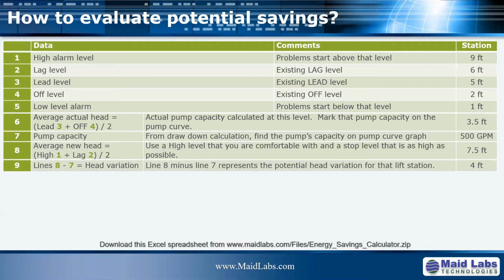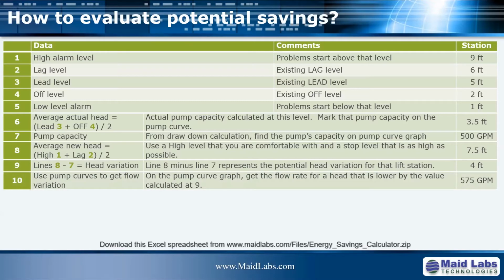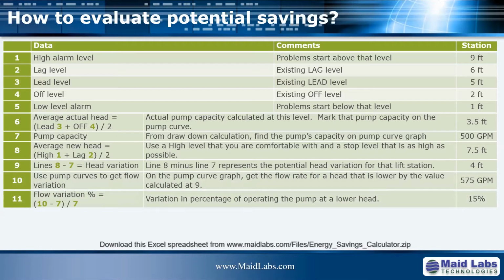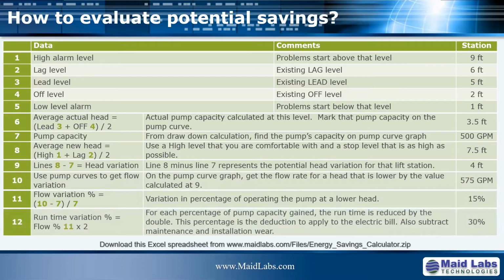That's what it means. So now that we know that we had 500 GPM, we look on the pump curve. Then we look at what would be the actual GPM we would gain if the head were 4 feet lower. Let's say that we arrive at 575 GPM. That would give you a gain of 15% in pump capacity by moving by 4 feet. This is based on your own pump curve. You have to use your pump curve to do that. So if you're increasing the pump capacity by 15%, you know that you're decreasing the actual runtime by 30%. And that's how you can really evaluate the kind of benefit you could gain by using this technology.